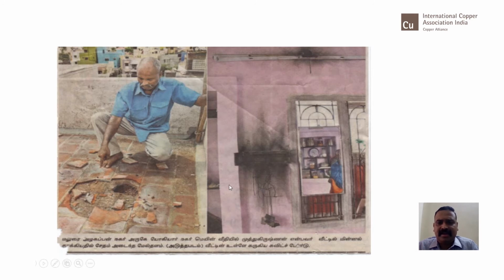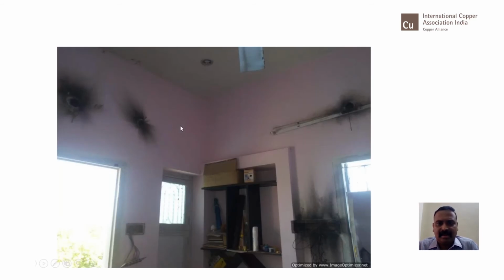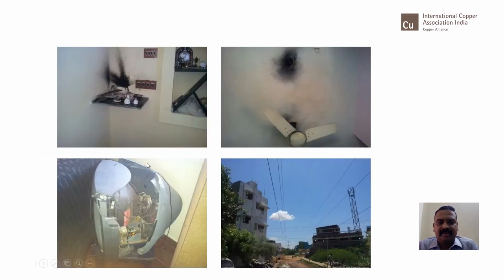On seeing this, we had a suspicion, because even if the current travels through the reinforcement bars, this particular switchboard and the light do not have a column nearby. The rebars obviously run inside the column, and since there is an absence of a column, this could not have directly impacted it. So we went to the site and understood. Almost all plug connections and all electrical junction points had burns, and not only that, every resident in that apartment had a failure. So then we investigated in detail what could have been the reason. What came to our mind, when we observed the site completely, was this is the building.